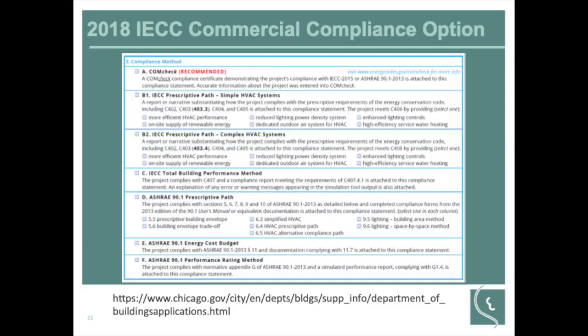For the commercial compliance options, once again, COMcheck is the recommended compliance path. It's a relatively simple and straightforward program to use. You enter in your U values, you enter in your equipment, and it checks it all against the code to make sure it meets. Again, it's important to realize that it follows a specific UA trade-off path and not the prescriptive path for envelope requirements. But you can also follow a prescriptive path for simple HVAC systems, a prescriptive path for complex HVAC systems, the total performance method, where you have to do better than a model building by a certain percentage, and the ASHRAE 90.1 prescriptive path.